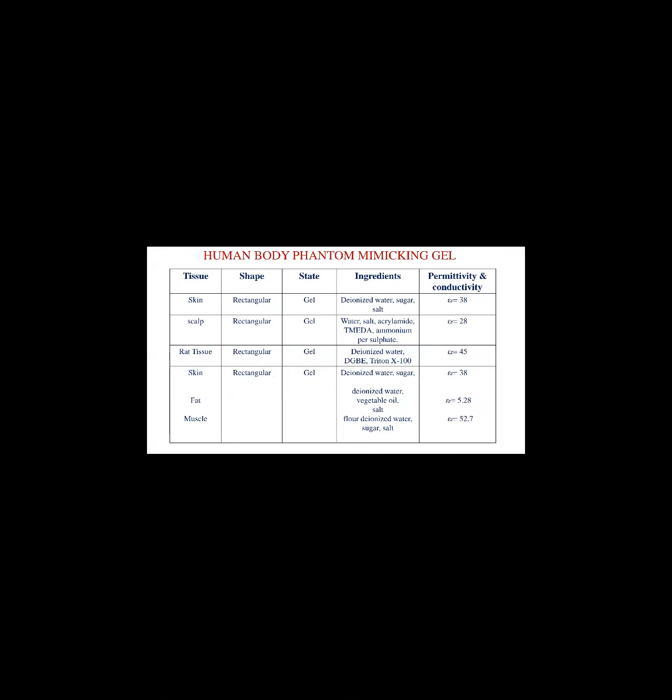For our design, we are using human body phantom mimicking gels. We have prepared different mimicking gels with different permittivity and conductivity characteristics. In general, we use a single-layer phantom or a triple-layer phantom. For the skin phantom, we prepare a gel by combining deionized water, salt, and sugar in different percentages to get the required dielectric permittivity.